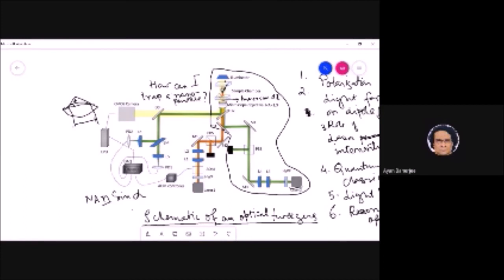That's a very important calibration strategy for optical traps, in order to see that the system is working the way you expect it to. When you increase the power of the laser, you see that the trapping force or stiffness increases linearly. Okay, what else?